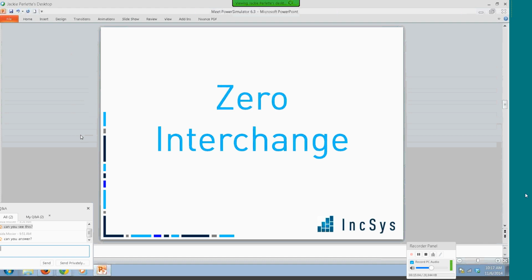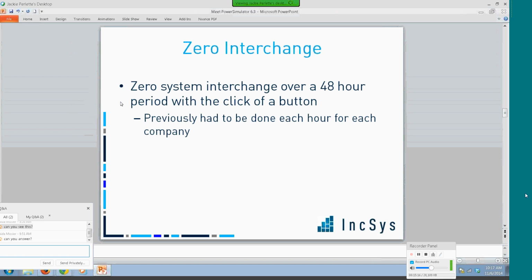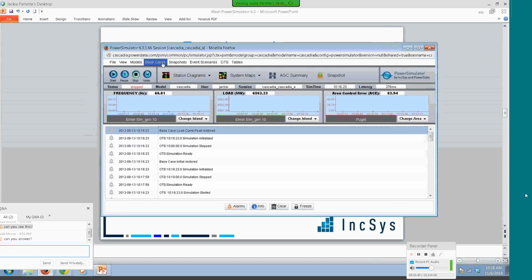One of the new features that we have implemented is the ability to zero your interchange. Previously, especially during a blackout condition or any kind of blackout restoration, every single one of your areas covers a 48-hour period. So there's a today-tomorrow interchange schedule that's set up. And if you want to change that, you have to change every single hour for every single control area. And if you have a lot of control areas or a lot of zones, that can take you pretty much forever. So what we have implemented in the new PowerSimulator 6.3...